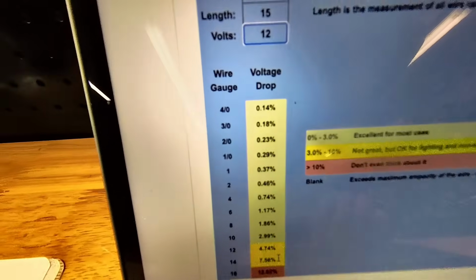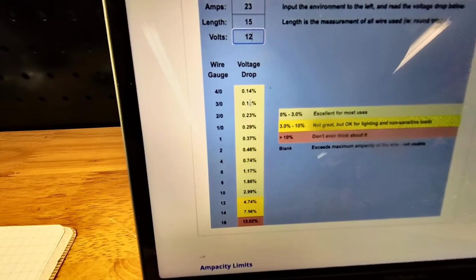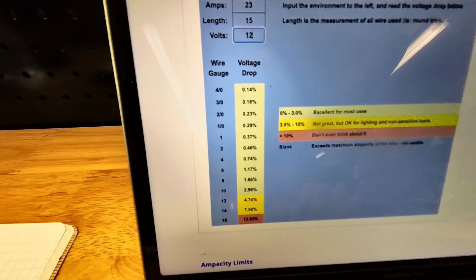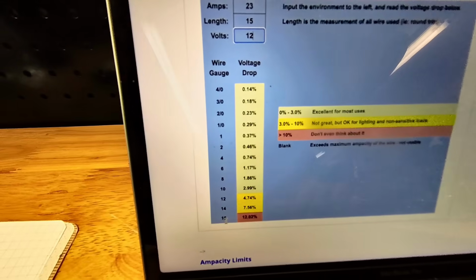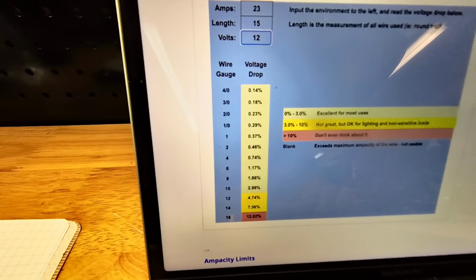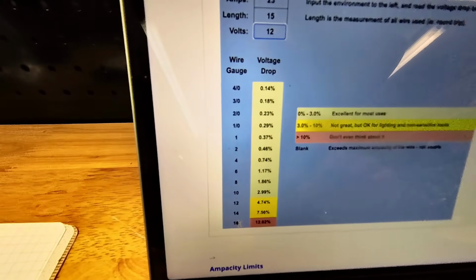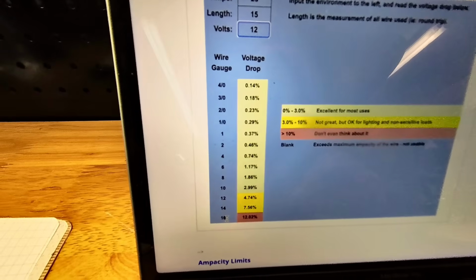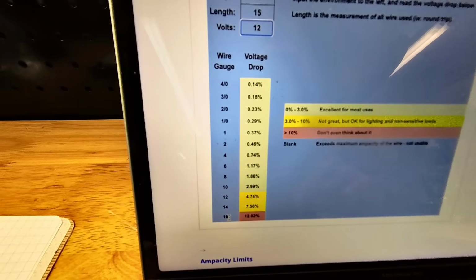These are voltage drop values based on wire size. If we start at the bottom of the chart, this is the wire size and gauge. Gauge is a little confusing because the larger the number, the smaller the wire actually is.